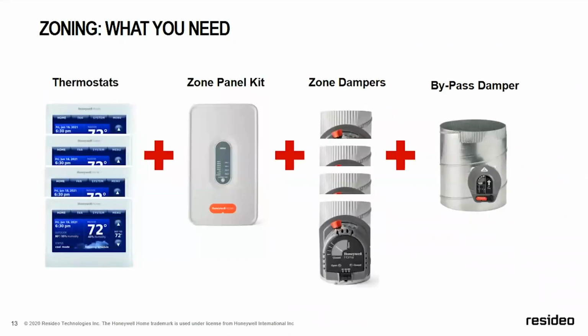Here's what you need. For every zone, you do need a thermostat. You can't use one thermostat and 4 wireless sensors and expect to do 4 zones. Then you need a zone panel kit. Now, why do we say a kit? We'll get into that a little bit more, but we always recommend a kit because you get all the pieces and parts that you need to make this work properly. Then you need the zone dampers, and a bypass damper is strongly recommended. We'll get into that a little bit later too.